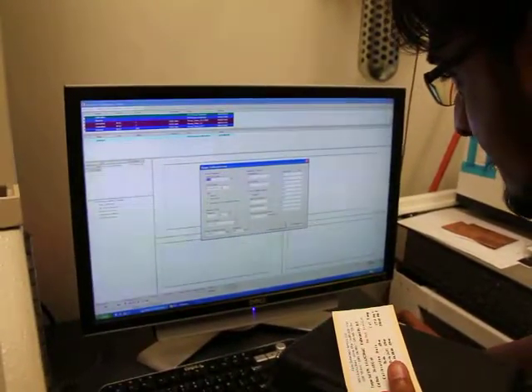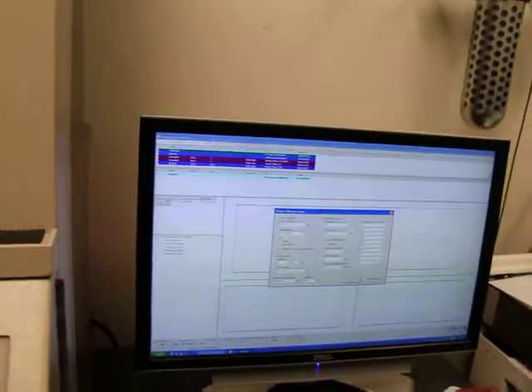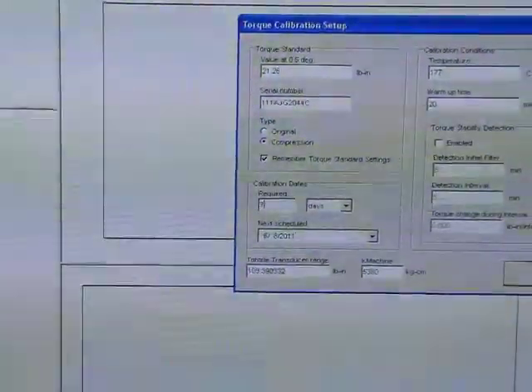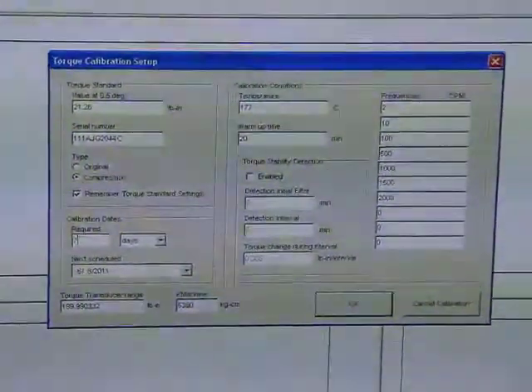So for calibration, what is the period for your calibration? How many days? Again, it depends on the amount of use, and I always calibrate before a specific study, and otherwise once a week. Should we keep all the study in the same calibration period, or doesn't it matter? When you're doing an aging study like this, I would always do a calibration before every data set, just in case there's some minor change. When you do the calibration, it sets the baseline, and that baseline should always be in effect the same. Right. Okay.